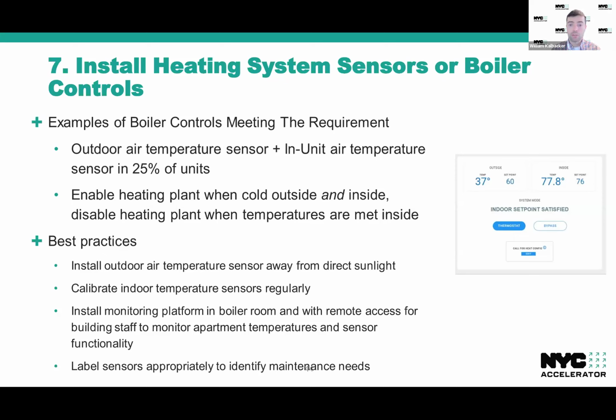and that when the indoor temperatures are satisfied, basically when it's warm enough inside, then the heating plant knows that it can turn off, even if it's still cold out, because it knows that it's done its job and that it can stop. Whereas if you just have a single outdoor temperature sensor that is modulating the boiler based on how cold it is, you very well might be overheating your spaces if the boiler can't get that indoor temperature feedback. Just some general best practices here.